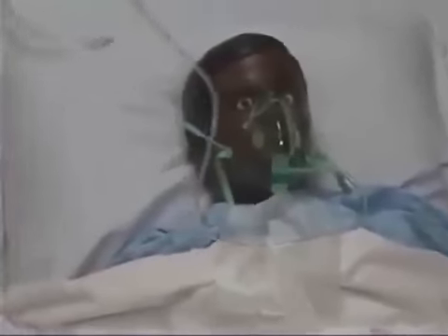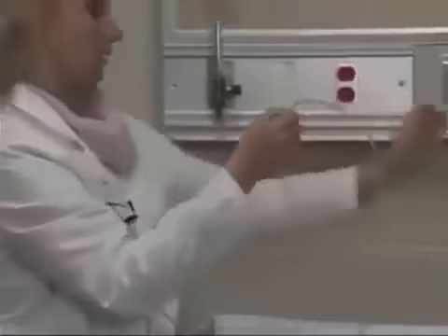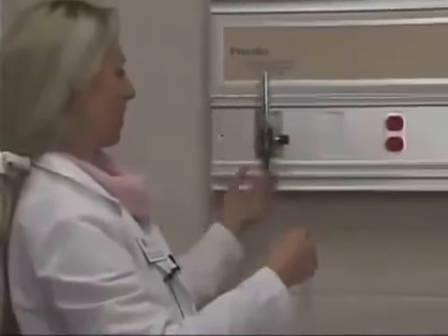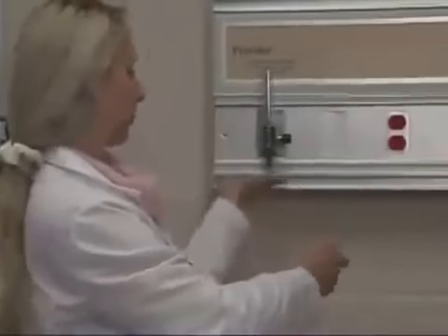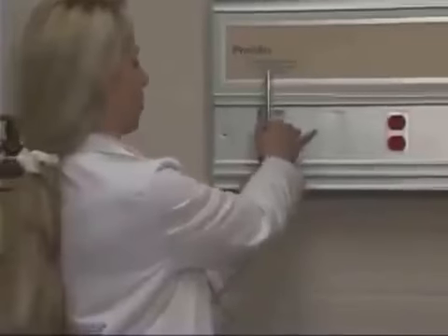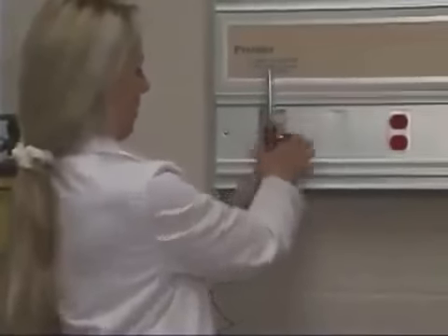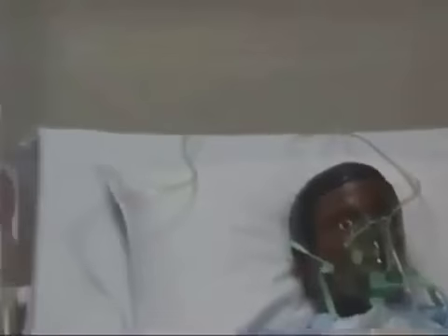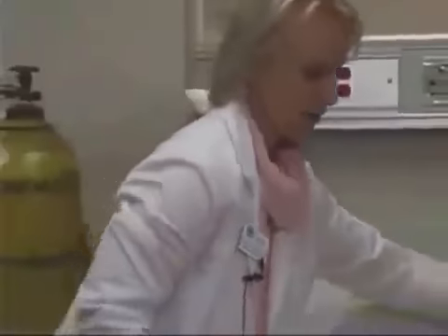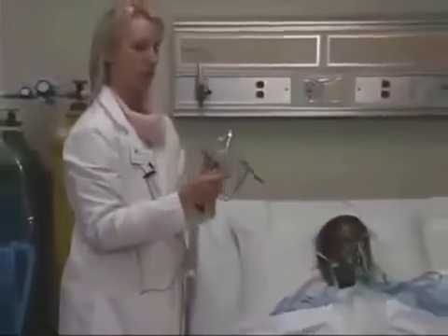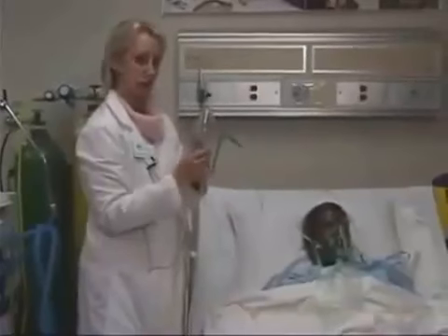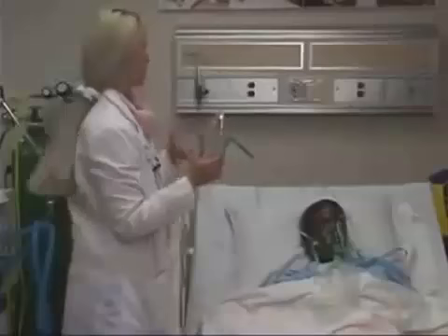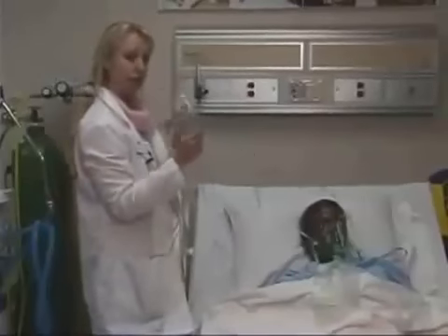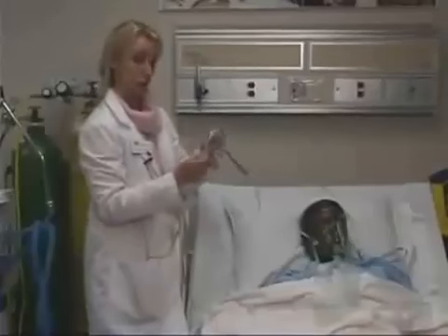And again, as with the other two devices, you're going to want to make sure that when your flow meter is on, you actually do have oxygen. You can feel a flow of air coming out of here before you attach this to your oxygen source. So you want to make sure that's secure. And again, with this partial rebreathing mask, you're going to want to make sure that the flow meter is set somewhere between 6 and 10. And similar to the simple face mask, respiratory therapy will measure how much oxygen is actually being delivered. And the respiratory therapist then may change that flow meter to make sure that the proper amount of oxygen that is ordered is actually being delivered.